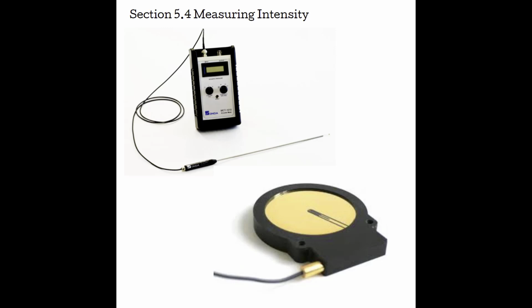The hydrophone is attached to an oscilloscope, and the hydrophone will be able to measure the pulse repetition period, the pulse duration, and the period of the wave. And from these parameters, as we've done in multiple examples in the past, we can actually calculate most of the other parameters of the wave. The hydrophone is capable of measuring amplitude, power, and intensity as well.